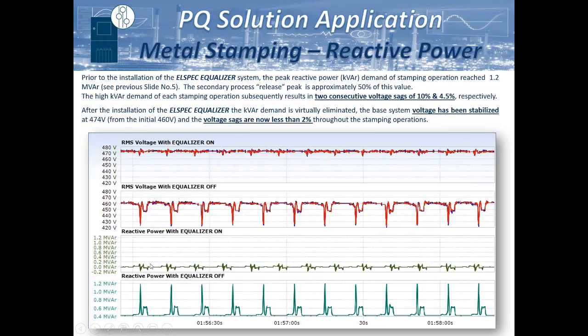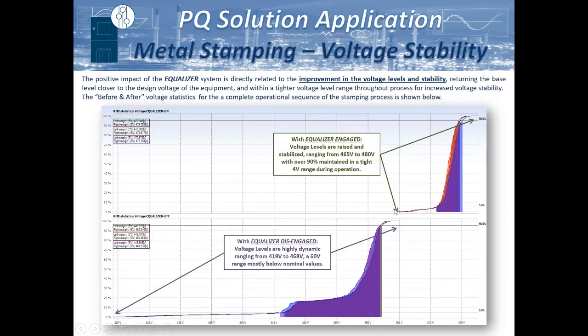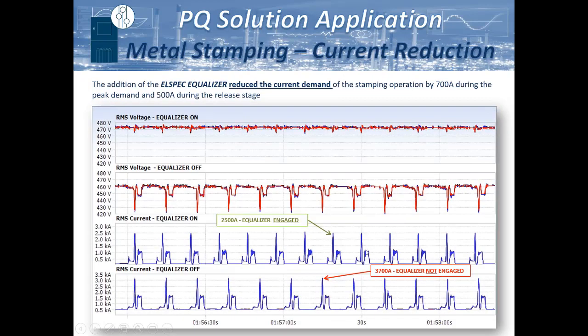allowing for the compensation. Here are the voltage levels on a statistical view. So this is the 90 percentile zone. You can see that there was a wide range in the baseline measurements, going anywhere from 419 to 468, versus the 90 percentile zone in here, which is about a 3 or 4 volt range. So we just keep it in a real, real tight tolerance area. And once again, on the peak currents, this all relates to heat, right? By stabilizing that voltage, it doesn't require as much current to perform its function. So a lot less heat is induced on that network, and heat leads to wear and tear, right?